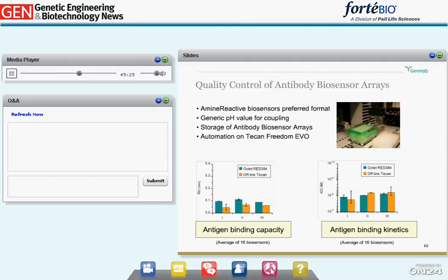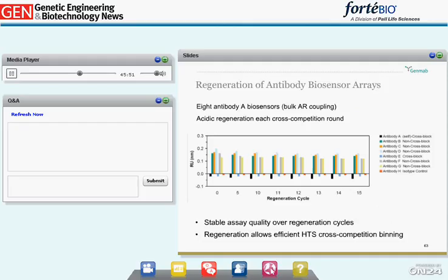Antibody biosensors can be generated either tray-wise on the Tecan platform or 16-biosensor-wise in the Octet 384 RED. When comparing methods by antigen binding capacity or antigen binding kinetics, we find no significant quality difference, while the Tecan-based tray-wise procedure is performed faster. To study the stability of antibody biosensor arrays towards acidic regeneration, we performed one and the same cross-competition analysis with one primary antibody coupled to biosensors, dipped into eight different secondary antibodies in 15 cycles with acidic sensor regeneration in between, seeing precisely the same results and sensor performance throughout.